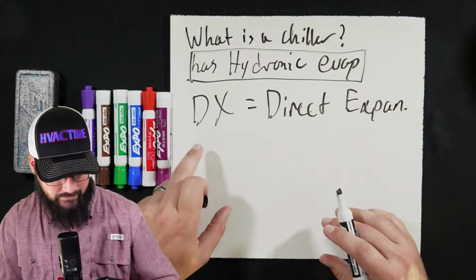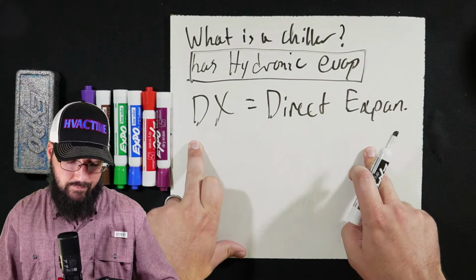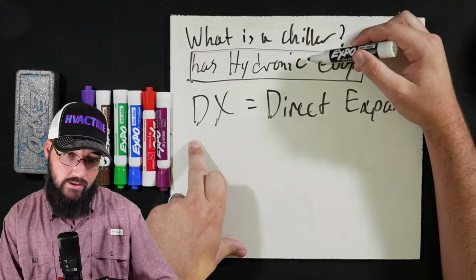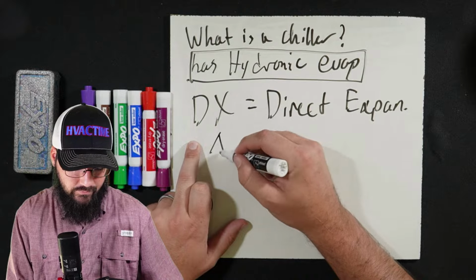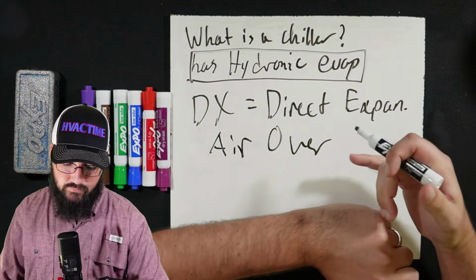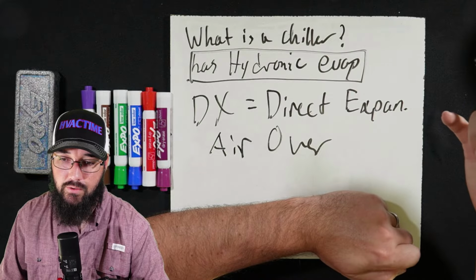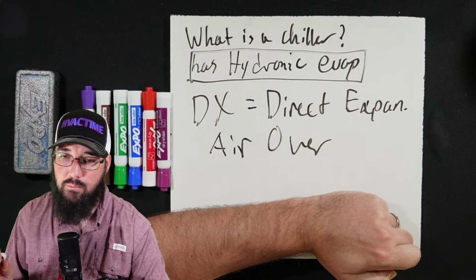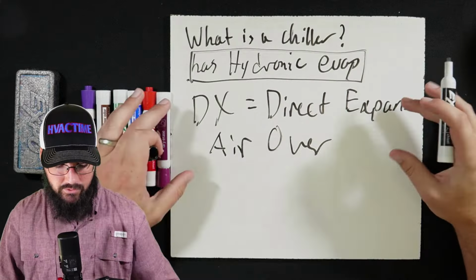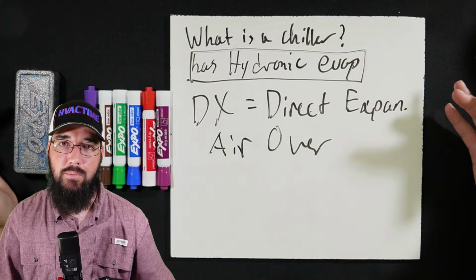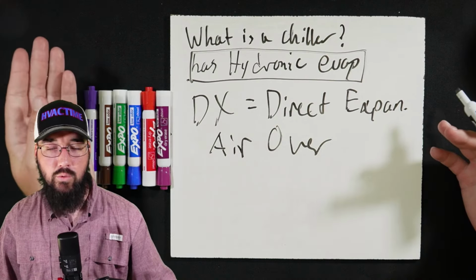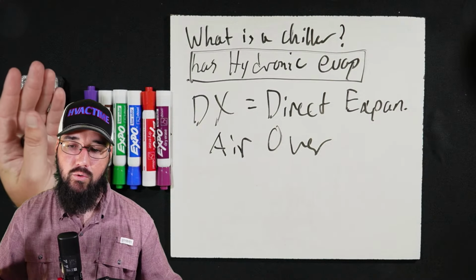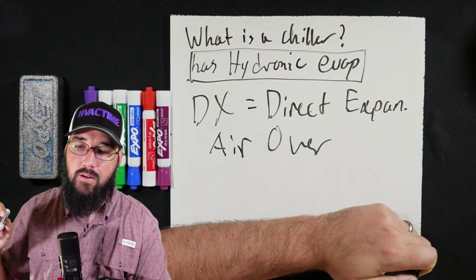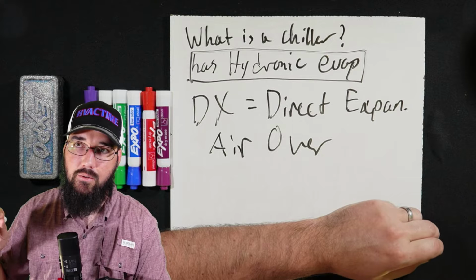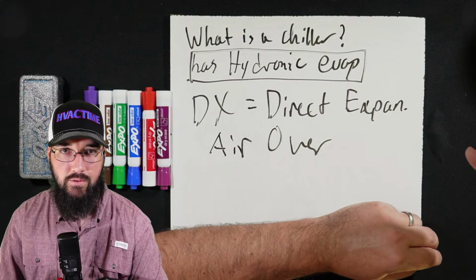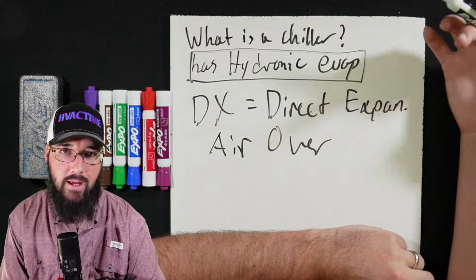Expand. That's close enough. We're saying a direct expansion system. So this, instead of being hydronic, is an air over coil. Now, the question was, with an air-cooled chiller, right? So now we're talking about the difference of, okay, we've basically got two rooftop systems. One makes chilled water, one cools the air. We have a DX system and an air-cooled hydronic system. They're both air-cooled. See, the DX units we have, they're also air-cooled.